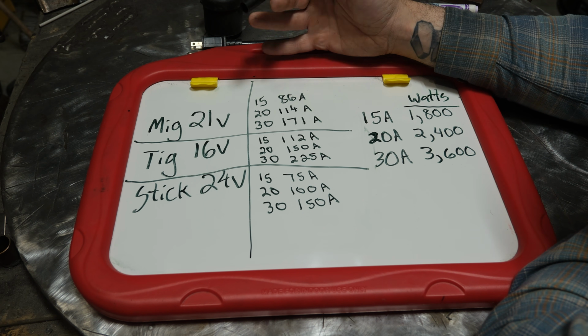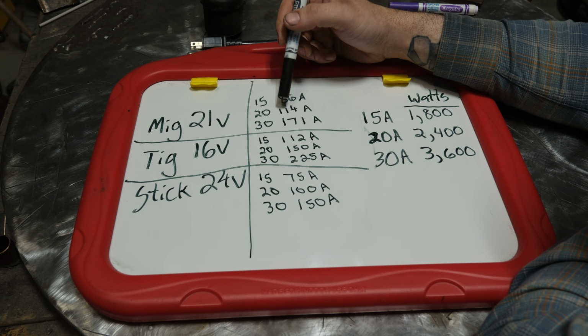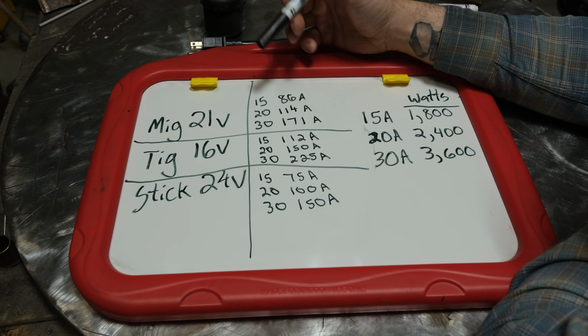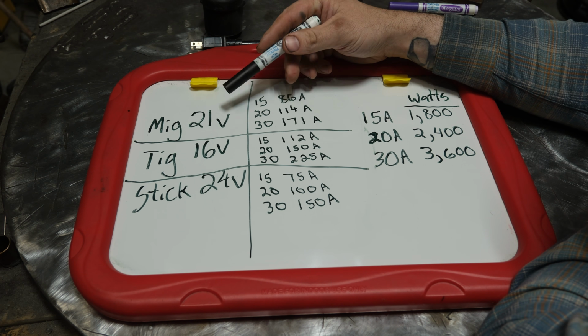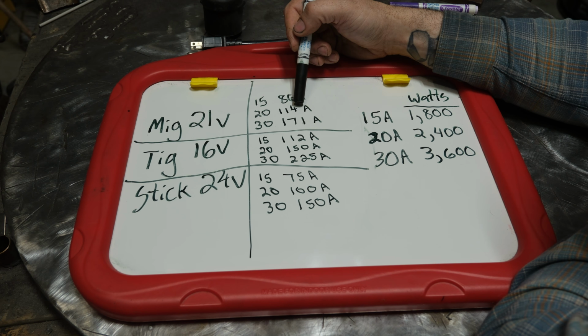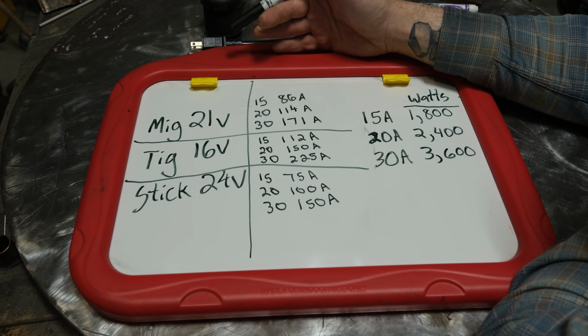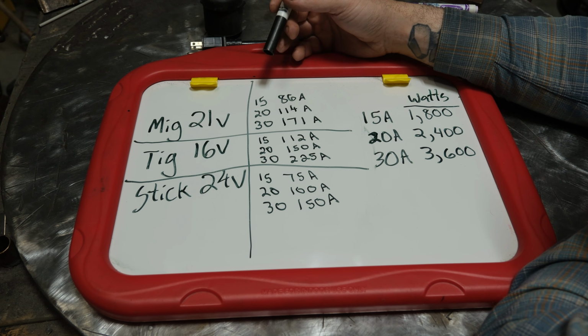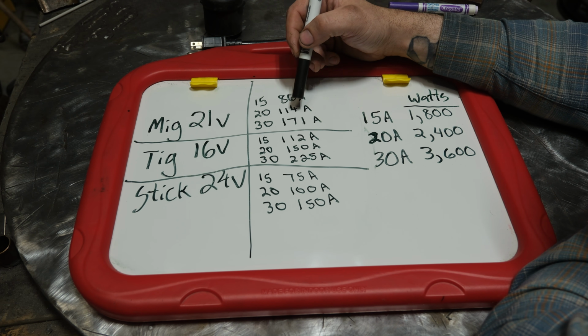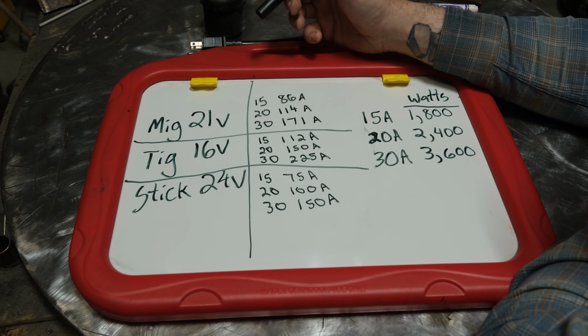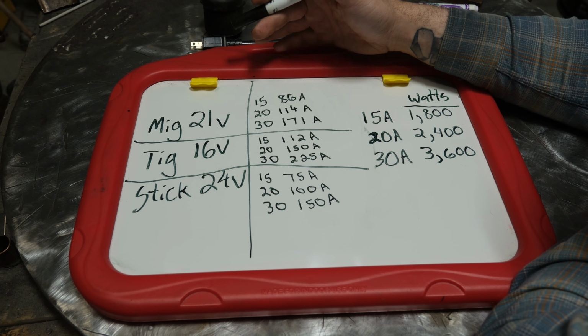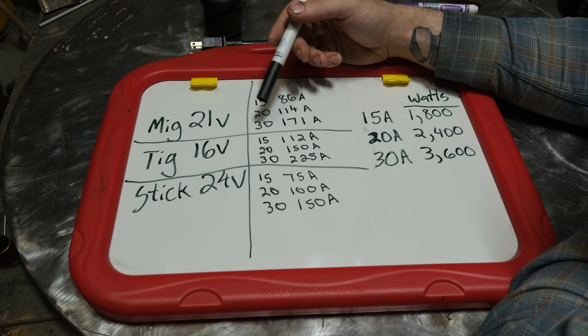So I hate to break it to you, all 120 volt welders overload circuits, because the theoretical maximum at 100% efficiency is 114 amps. That's all the power that is there by the breaker's rating. You have to overload the breaker to get to a higher output level. That's just how it is, okay? So now let's look at the TIG.